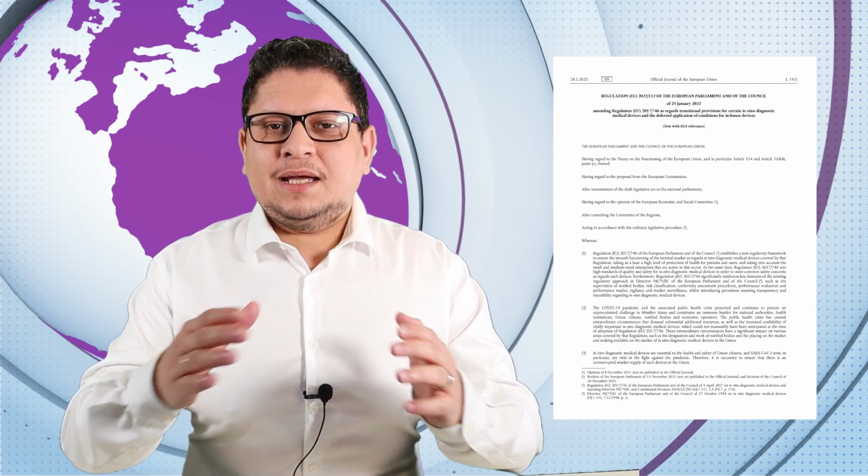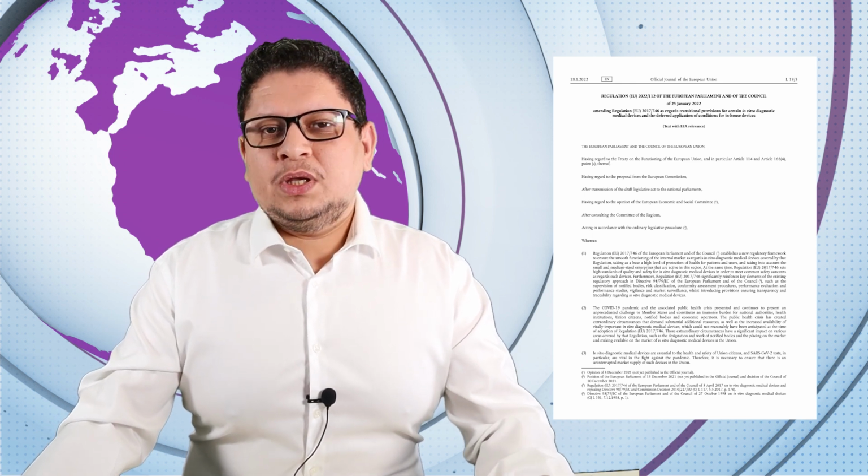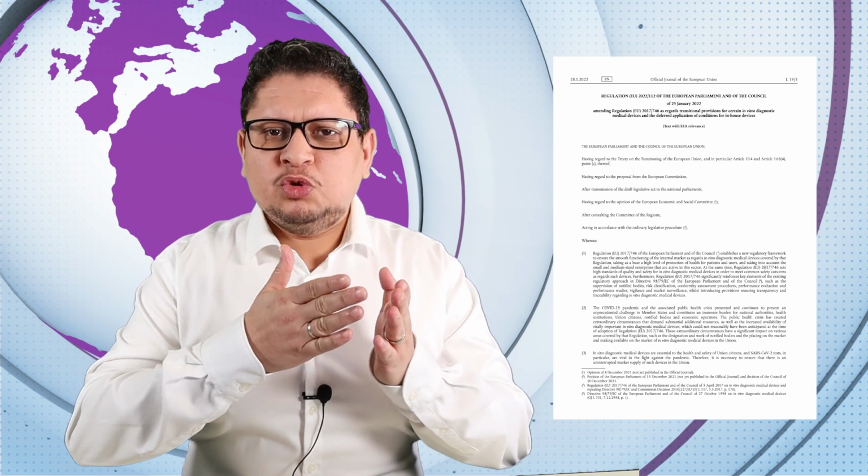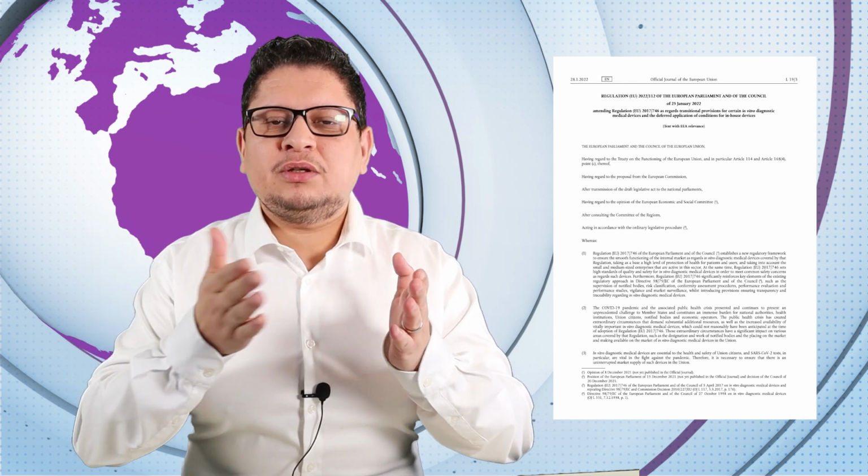One thing you have to be clear about is that if your product follows the IVDD and has a transition period from the 26th of May 2022, then during this period, between the 26th of May 2022 and the real date for your products, if you have any significant change to your product, it has to comply with the IVDR immediately. It is the same rule as for MDR, so this is something you have to understand.